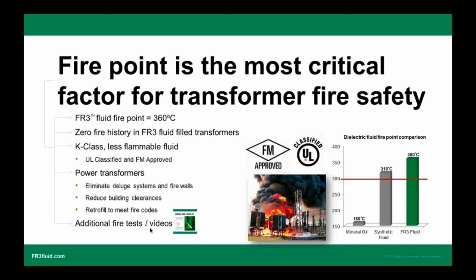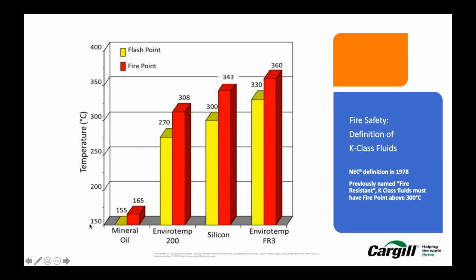Now, what is the logic for 300 degrees C? There are a lot of calculations and empirical formulas for why it has been locked at 300 degrees C. But to cut short the discussion, when IEC came up with this classification, all the fluids, including silicone, synthetic ester, and natural ester, which have a fire point above 300, are classified as K-class, and all three fluids give equal fire safety. Now, I am saying equal fire safety in terms of a fire. In terms of usability, we will see in detail further. So let's move to the next slide.